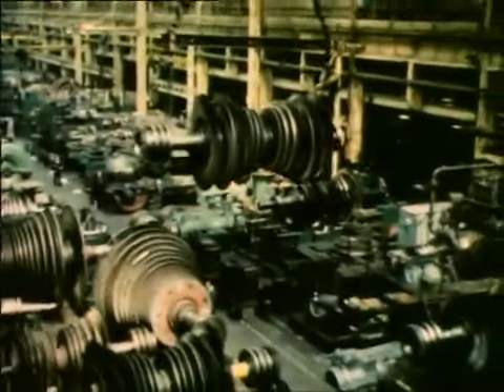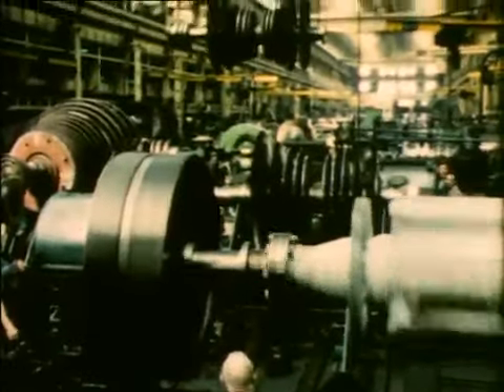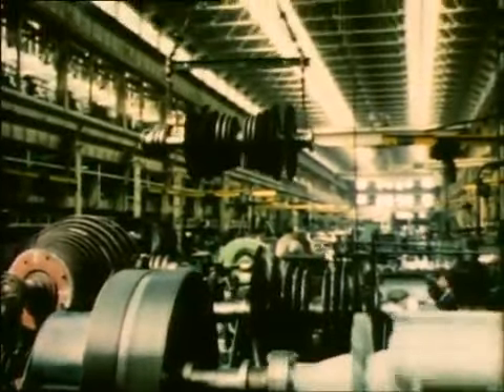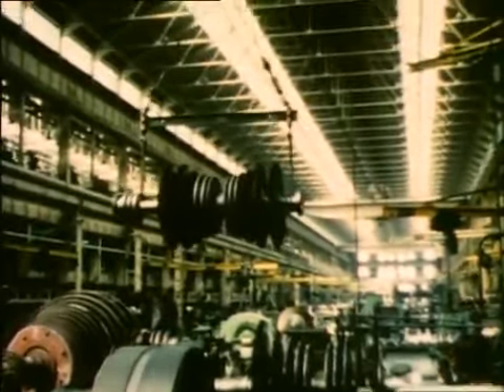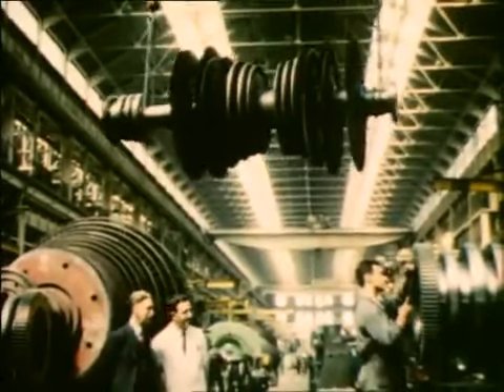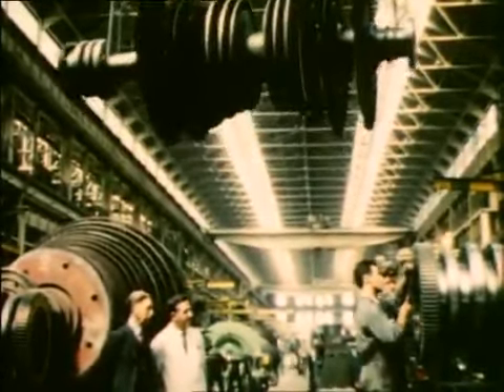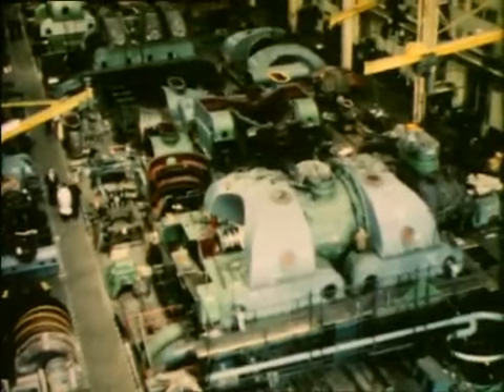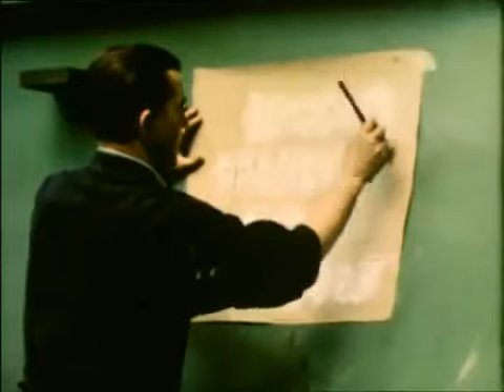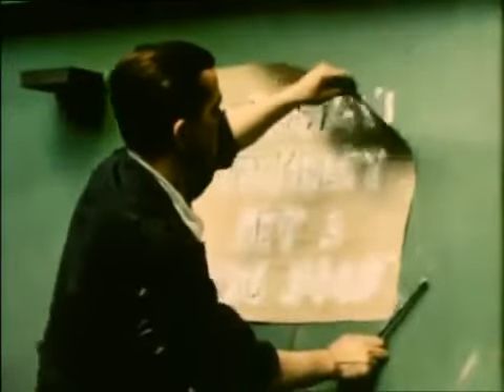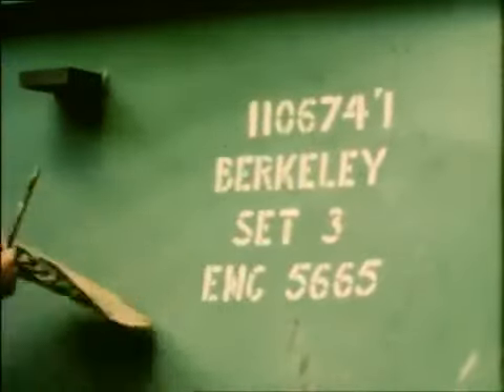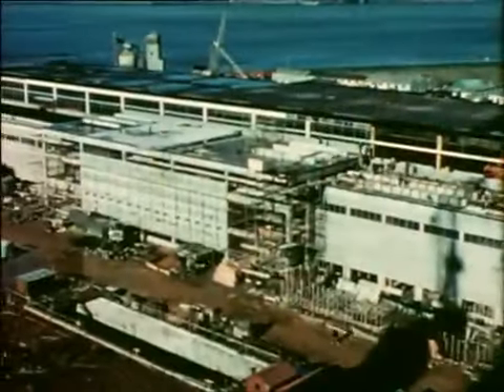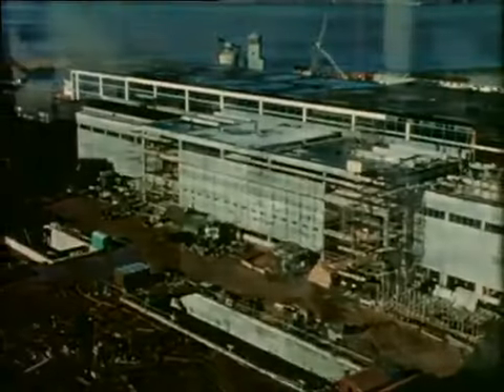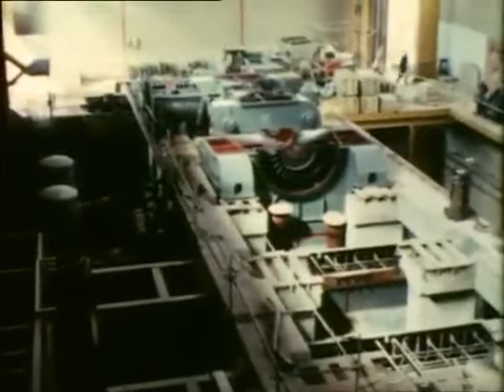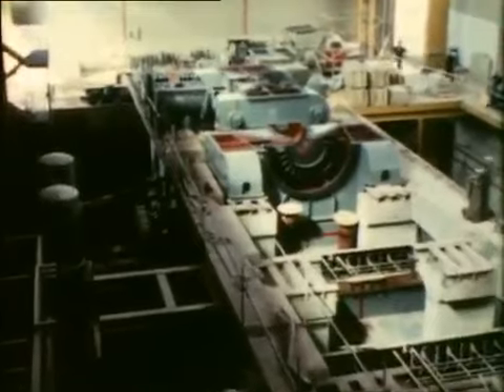The 4 turbo alternators were constructed at Manchester. They're 3,000 revolutions per minute machines designed to accept steam at 2 pressures generated by the boilers. The alternators are hydrogen cooled and generate at 11,800 volts. After assembly and testing, the turbo alternators were installed on the concrete turbo blocks which form part of the turbine hall foundations.